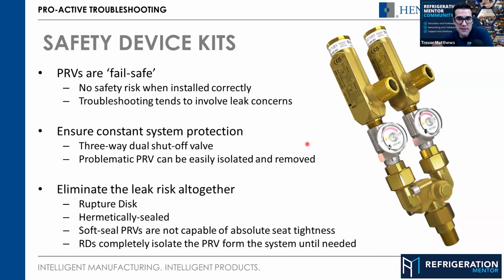So if you just have a spring type, it's going to leak a little bit. You know what I mean? So you go up with your leak detector, pick it up, you blow it out, and then all of a sudden there's no leaking. I have this question from people. Well, if it's on the roof and you're outside and it rains or snows and that fills up with water, how does that affect the PRV if it's in the elements like that? Yeah, so you should always avoid that, the valve filling up with water, especially snow, even worse.